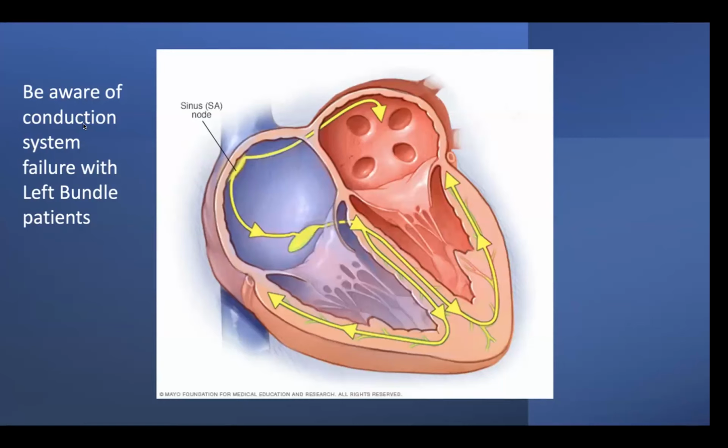So I think asynchronous, and feel free, Elvis, Jared, Dr. Dafe, to chime in here and correct me, but I think asynchronous is your friend in those cases where you risk a little bit of competitive pacing, or you risk a possible pacing into T. But for a dependent patient, I think it's always better just to capture. So making sure that your device is set asynchronous, possibly both devices.